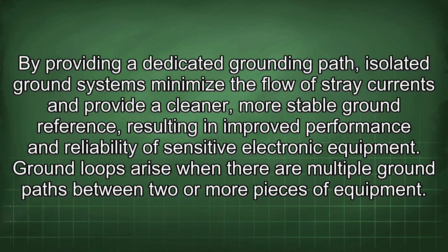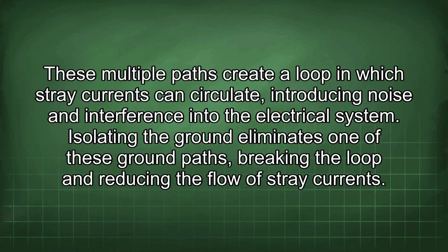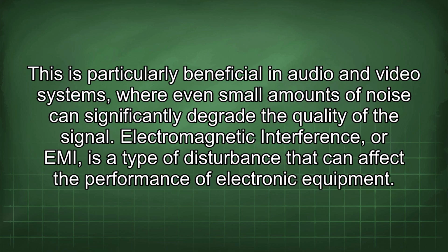Ground loops arise when there are multiple ground paths between two or more pieces of equipment. These multiple paths create a loop in which stray currents can circulate, introducing noise and interference into the electrical system. Isolating the ground eliminates one of these ground paths, breaking the loop and reducing the flow of stray currents.